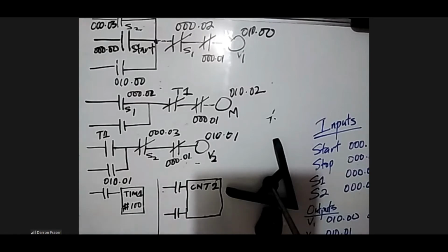We say we want to count 5 loops. So therefore, we put the number sign, and this time we put the number sign on 5. We don't have to put a 0 on it, because all it is doing is registering every time our switch is closed or our sensor, whatever it is. So we can just put 5. For the timer, you put an extra 0 if it's 10 seconds or so, but if you count in 5, you just put the number sign on 5.